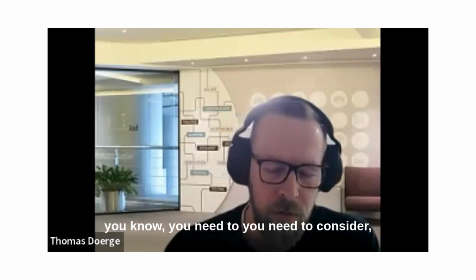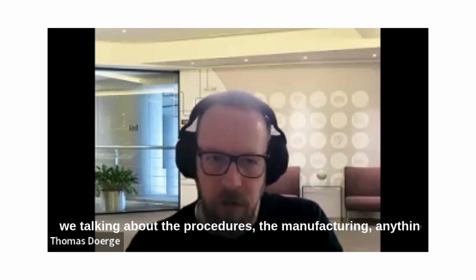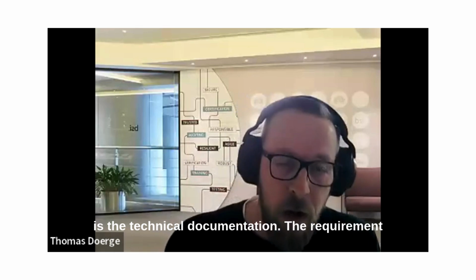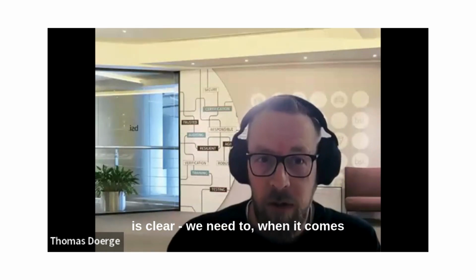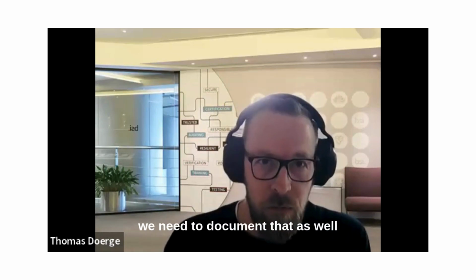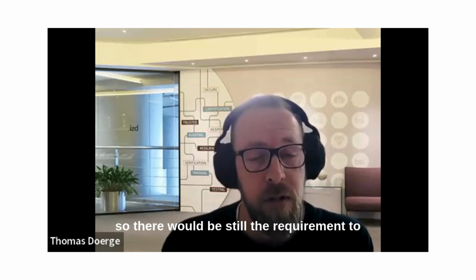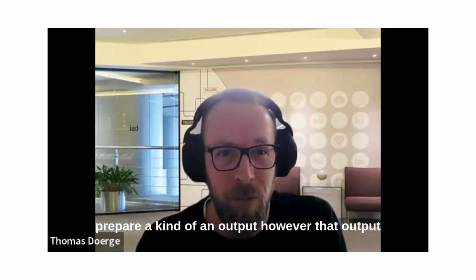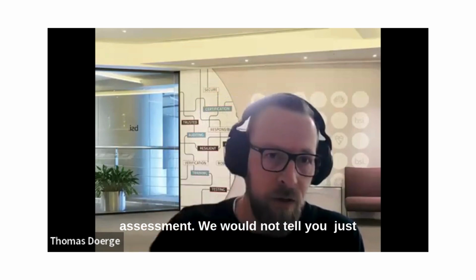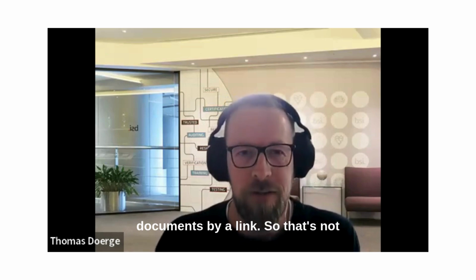You need to consider that's the quality management system part: the procedures, the manufacturing, anything behind that. The output is, at the end of the day, part of the technical documentation. The requirement is clear: when it comes to the technical documentation, we need to have a set of documents in front of us, because we need to document and save that. So there is still the requirement to prepare an output, however it looks, to be sent over to the notified body so that we can perform the assessment. We would not tell you to just give me access to your internal technical documentation and I will access the documents via link. That's not possible.